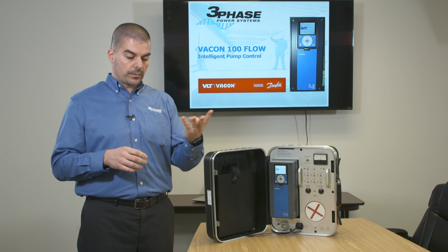We want to monitor output frequency. We want to know how fast the motor is running. Great. We want to monitor what the pressure feedback is and what our set point is. The drive actually displays PSI. It can display any number of different monitoring values: flow, pressure, temperature, you name it, we can monitor it. We want to know what the feedback of the pressure is doing in terms of the analog 4 to 20 milliamp input, which can be found in the third spot here.